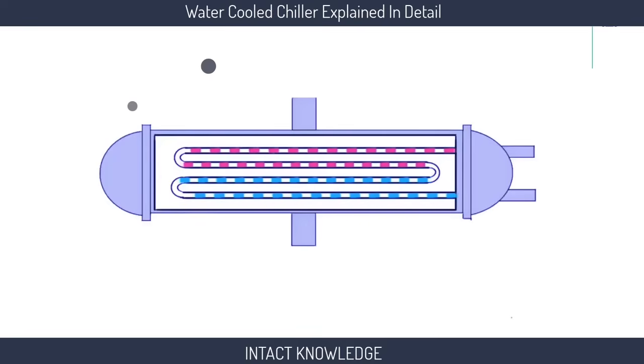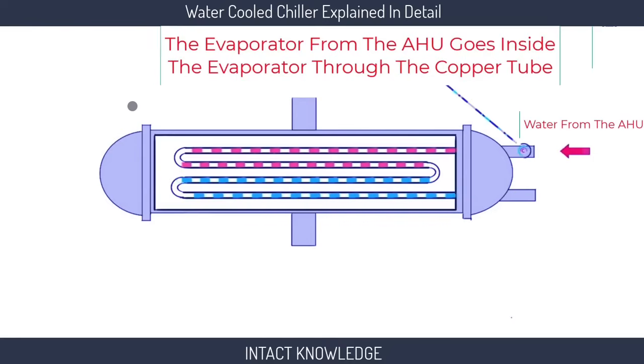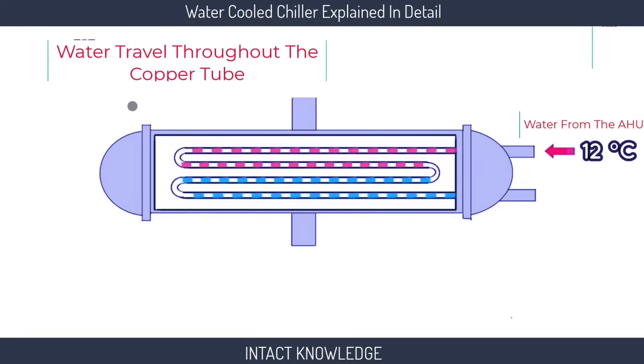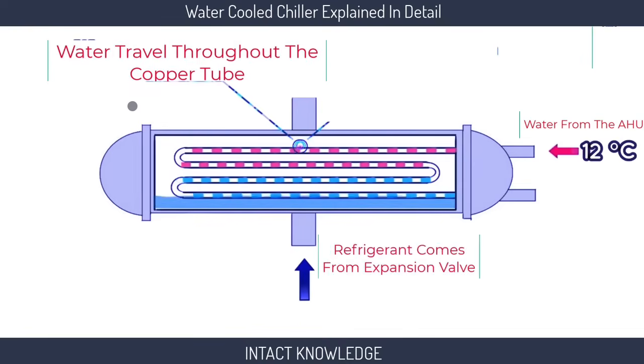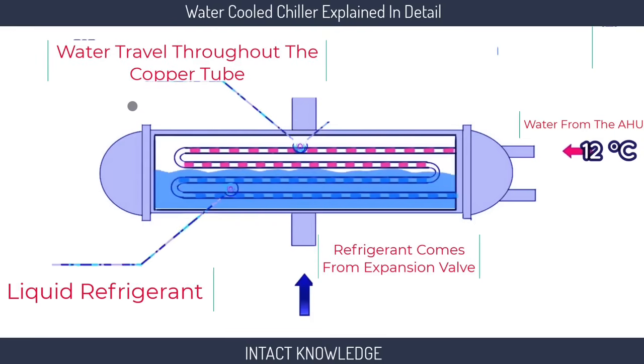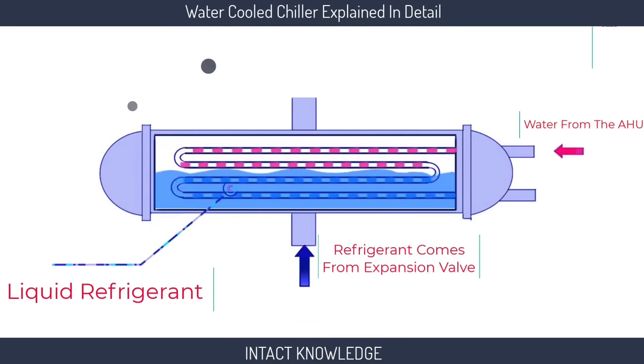Next, the refrigerant will enter into the evaporator. The evaporator is also similar to the condenser. In the condenser, the water from the cooling tower enters through the coil. But in the evaporator, the water from the AHU enters through the coil. The water from the AHU will enter into the evaporator at 12 degrees Celsius and it will travel throughout the coil. The refrigerant that comes in cold from the expansion valve surrounds the coil inside the evaporator.